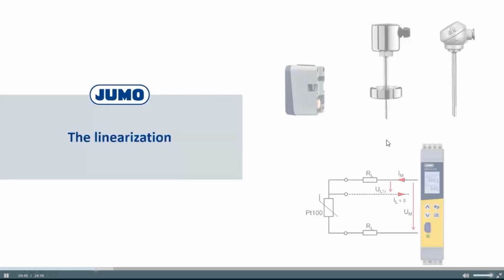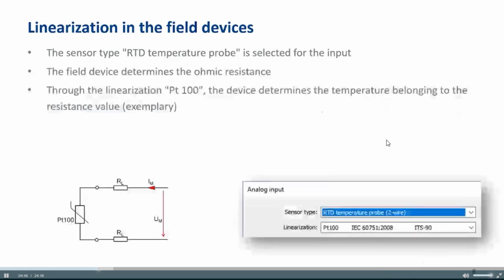Then let's look at a few words about the linearization. So you have a PT100, a PT1000. How can you get the temperature from this RTD temperature probe? If we speak about JUMO devices, for instance, most of our devices offer universal analog inputs. So you can connect current signals, voltages, thermocouples, and RTD temperature probes. And if you connect an RTD temperature probe like a PT100 to such a device, then you look at the corresponding analog input.